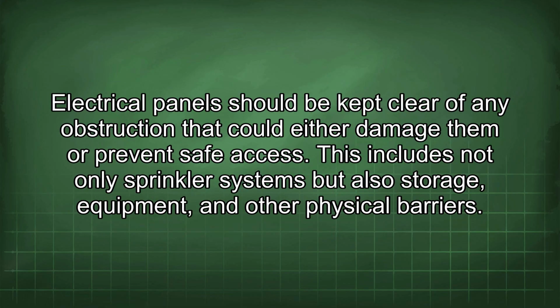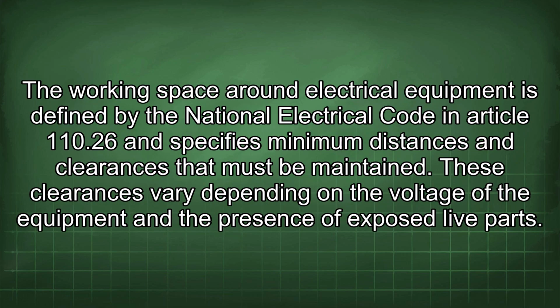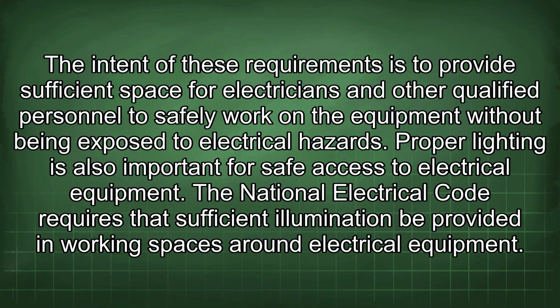Electrical panels should be kept clear of any obstruction that could either damage them or prevent safe access. This includes not only sprinkler systems but also storage equipment and other physical barriers. The working space around electrical equipment is defined by the National Electrical Code in Article 110.26 and specifies minimum distances and clearances that must be maintained. These clearances vary depending on the voltage of the equipment and the presence of exposed live parts. The intent of these requirements is to provide sufficient space for electricians and other qualified personnel to safely work on the equipment without being exposed to electrical hazards.